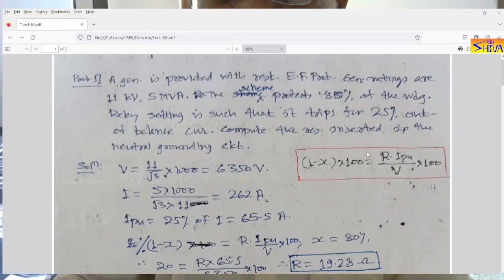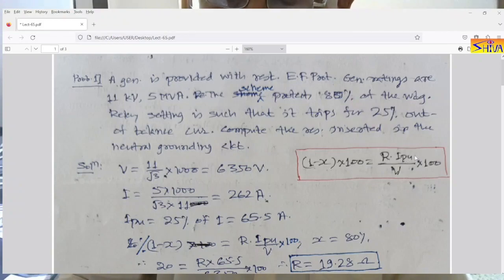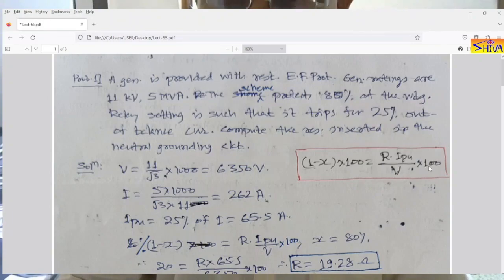For restricted earth fault protection of the generator, we have derived one equation for the percentage of winding unprotected. Here x is the winding protected. So if we multiply this by 100, the percentage of winding unprotected is equal to R (neutral grounding resistance) multiplied by I_pickup (the pickup current from the primary side of the CT), divided by the phase voltage of the generator, multiplied by 100.